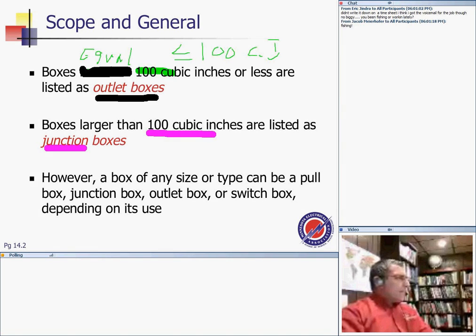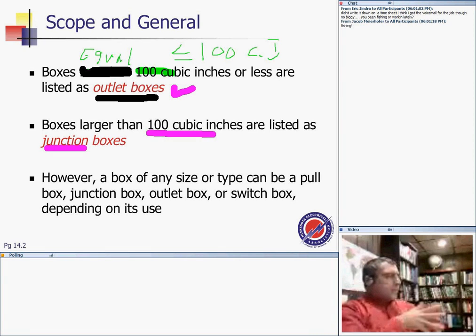Now, can I use a J box as a device box? No problem. So this definition doesn't mean a whole lot, because you can use a J box as an outlet box, or an outlet box as a J box. But for the most part, in a device box you put a device in it. In a J box, you terminate for a light fixture, terminate conduits into it, connect the phases, switch from one direction to another, and so forth. It's mainly meant to provide an outlet there, a receptacle outlet, switch outlet, any type of device. If it's a J box, for the most part, it's meant to terminate circuits going in different directions.